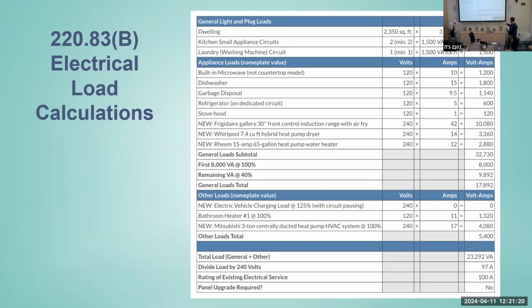Anyway, skipping to the end here, we take the total from this section and the total from that section and add them together. In this case, it comes out to 97 amps. So this house is just right under that 100 amp threshold, but it's fully electrified.